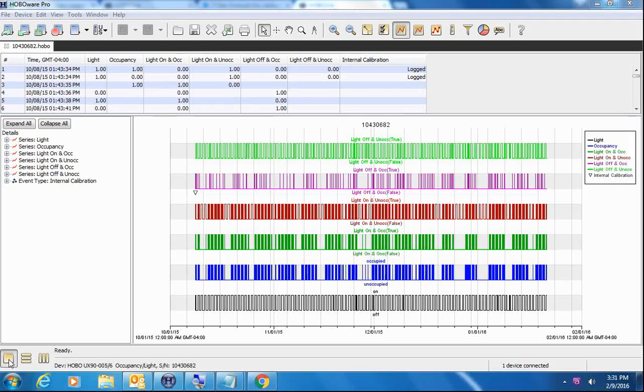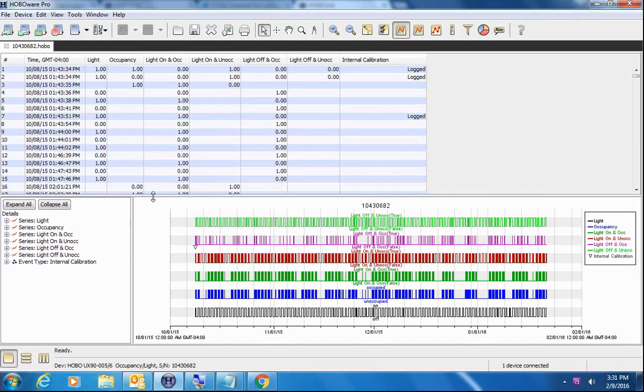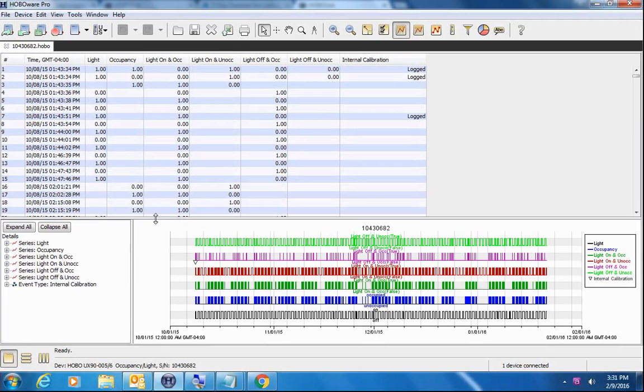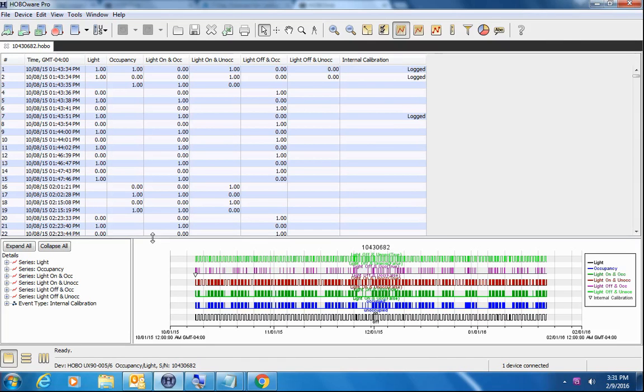Here we have our light on off and occupied, unoccupied data plotted. You can see here in the data table everything is recorded. This was not runtime, runtime was not selected, so we're not tied to an interval. We were just logging state data. So that gets us down to that one second resolution. We're always at a one second resolution.